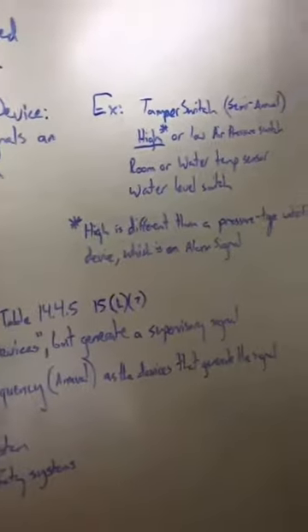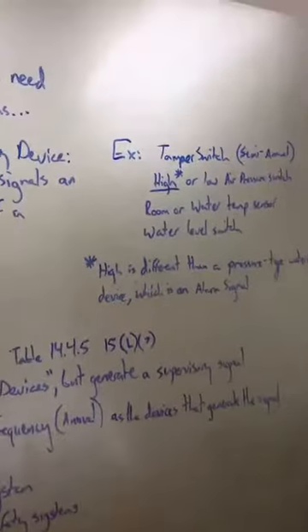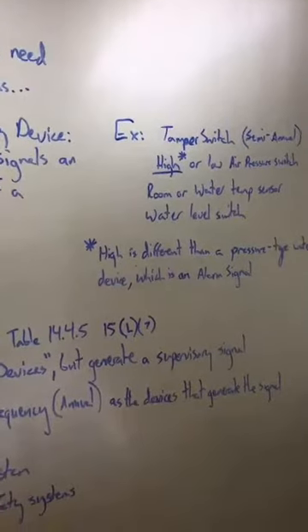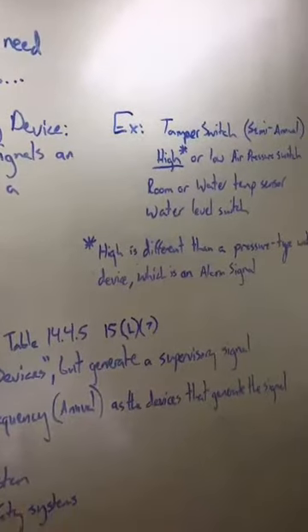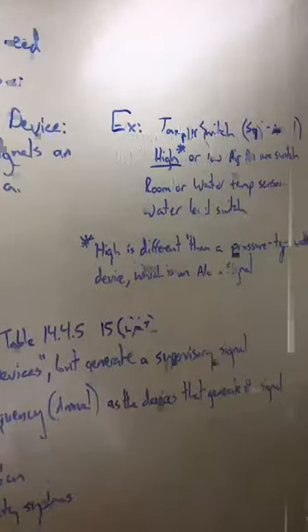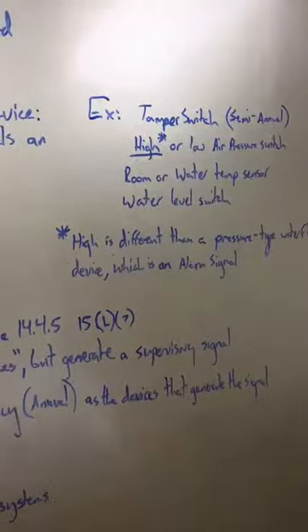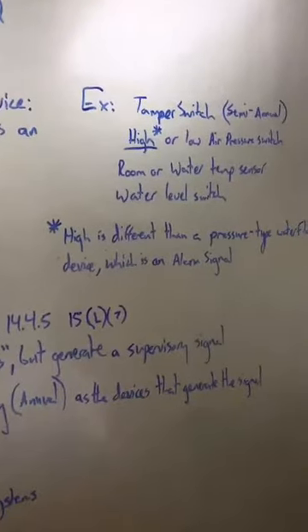I specifically wanted to identify the high air pressure switch as a supervisory is different than a high pressure type water flow device. So when your dry pipe system is filled with water, it triggers an alarm signal, which is a pressure type water flow device. That's different. So understand which ones are supervisory and which ones are alarm.